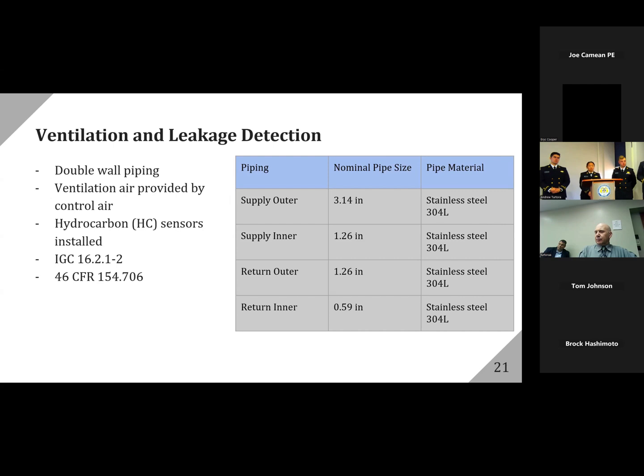And anytime you have gas as a fuel, class will make you do a hazard review of all of the systems in the engine. From where am I venting this fuel? How am I detecting fuel leaks? To what ATEX or IECEx ratings do I have on my equipment? They're going to want to see all of that stuff. So it would have been nice to see if you had any equipment that needs ATEX or things like that, and what the zones are.